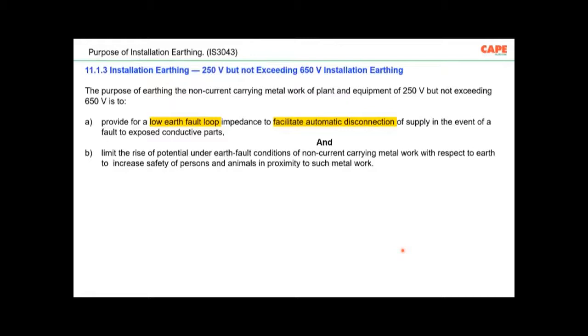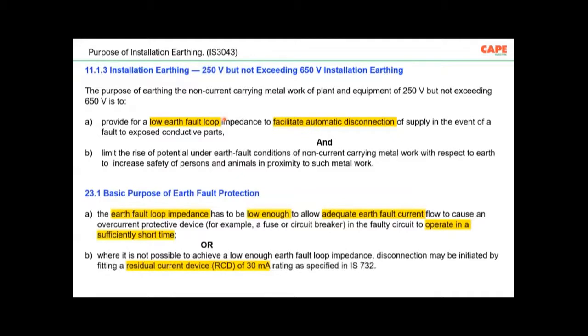IS 3043 11 clause 11.1.3, what does it say? The purpose of earthing the non-current carrying metal plant and equipment of a 250 volt but not exceeding 650 volt is, please read the highlighted portion. Provide a low earth fault loop impedance to facilitate automatic disconnection of supply. Then the second purpose is to limit the rise of potential. So basically, earthing in an installation has got two purposes. One is to make a very low fault loop impedance connection so that your equipment is able to disconnect in case of a fault, and the second is to reduce the touch voltage.